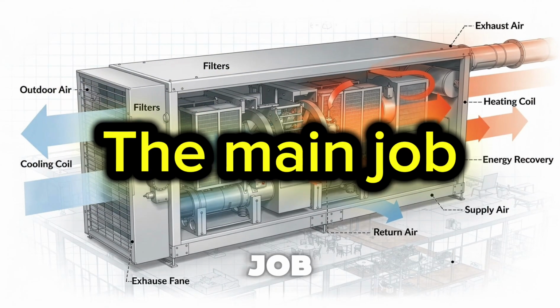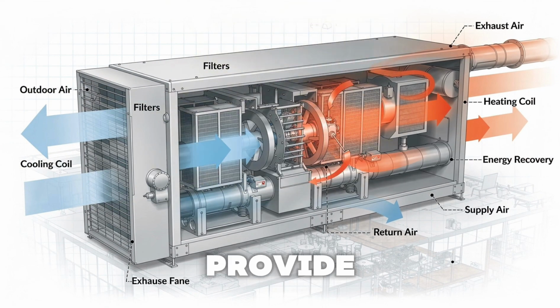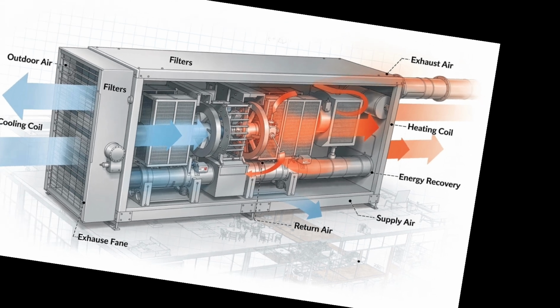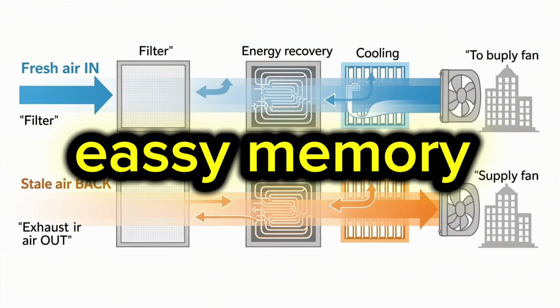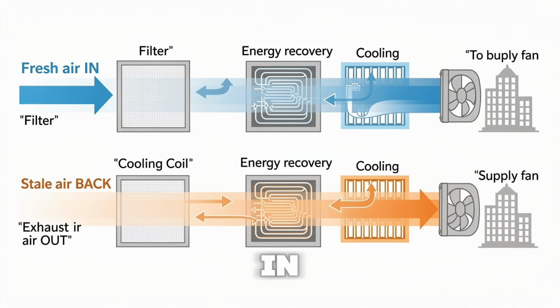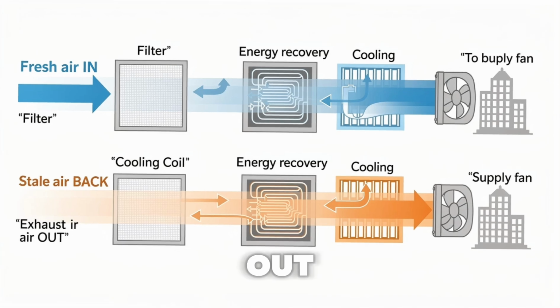The main job of a FAHU is to provide clean, conditioned, fresh air while removing stale air and recovering useful energy before it is exhausted. Easy memory. Fresh air comes in, gets filtered, recovers energy, gets cooled, supply fan sends it to the building. Stale air comes back, gives up energy, gets exhausted out.